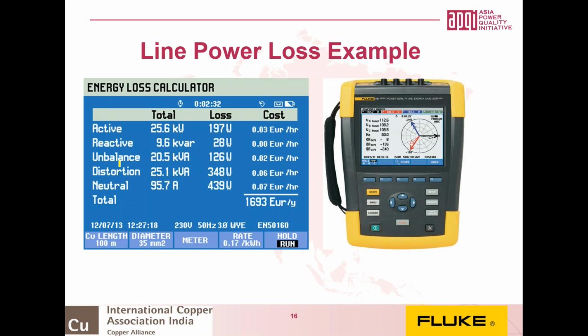Then we have the unbalance power and the loss caused by the unbalance, and then the distortion or harmonic losses, and then finally the neutral. This is a simple calculator. We're currently improving this, but it uses the unified power method to take each of the separate components so that we can really make a good judgment as to where you should make investments in your electrical system.